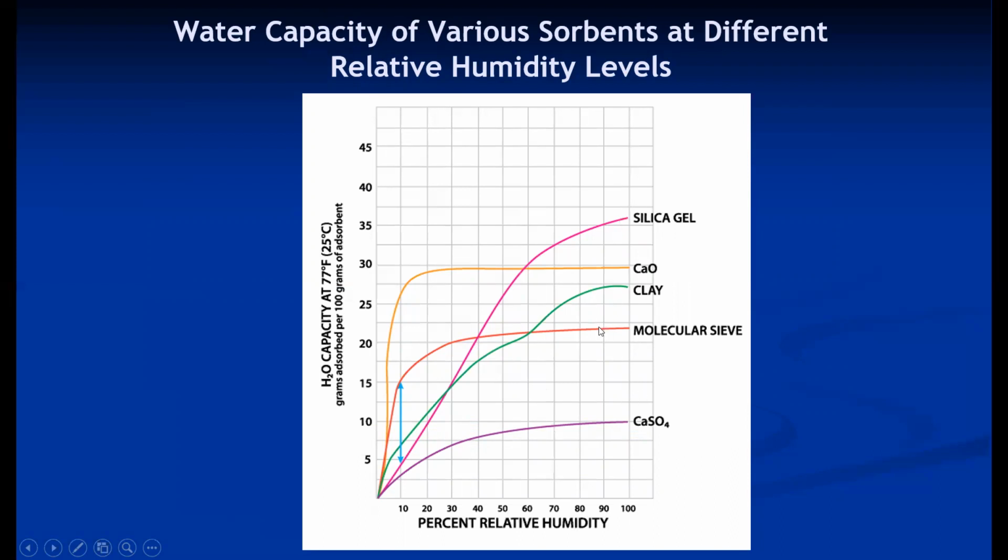But if we have to use these desiccants for low humidity applications, generally below 60% humidity, then calcium chloride, calcium oxide is best amongst all. So this is a graphical characteristics of this desiccant. So that's why silica gel is extensively used as a solid desiccant for humid climate.